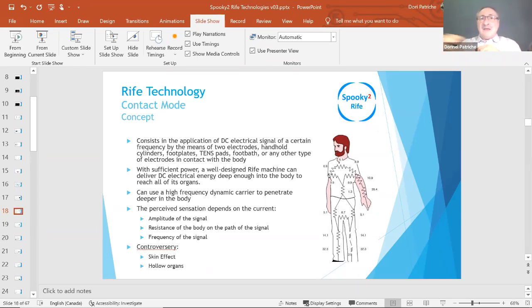The sensation perceived by a subject during a contact mode session is proportional to the amount of current that goes through the body. The current itself depends on two factors. The first, as expected, is the amplitude of the signal. This value is set up by the software, but it can be modified by the user in the settings tab. The other factor is the resistance of the body. As you can see in the image on the right, you have different values of the resistance depending on which points we are measuring it. The resistance depends mainly on the placement of the electrodes. The farther apart the electrodes are, the higher the resistance value and the lower the current.